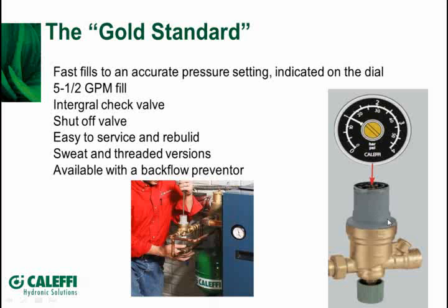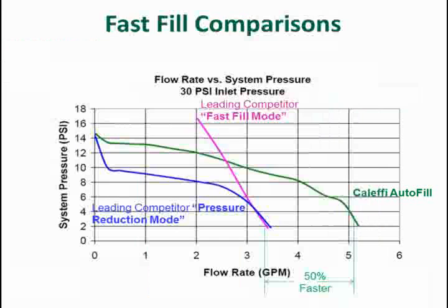Put channel locks on that, take the top off. There's a nice strainer around the whole diameter of this, so it's got a lot of surface area. Any dirt and debris that comes in through your fill system, that got through your piping in the house and so on, we're going to catch it before it gets into the regulator, into the diaphragm here, and into the shutoff valve down here. So take it apart. You can replace the cartridge. You can clean out the strainer. And it's available in a sweat or threaded version over here. We also have it put together with a backflow as a combination system. I'll show you in the next picture.